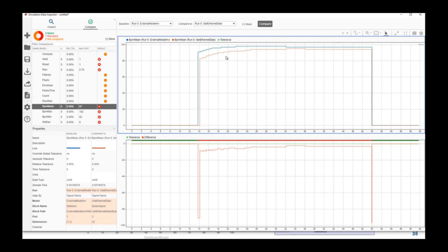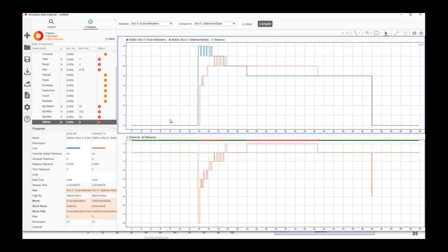And so these are the two signals. In the second measurement, we can see that my frequency rate was a bit lower. And I can also see the standard deviation, for example. Here you see at the end, the error on the measurement is the same. We have just ±5, which is fine. And you see with this kind of interface, you can quickly compare the measurements that you did with the baseline that has already been set up for the specific test you would like to do.